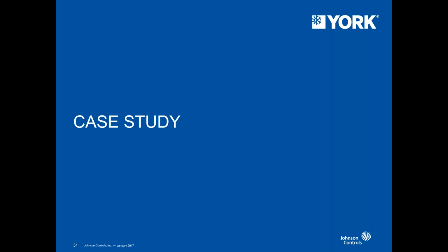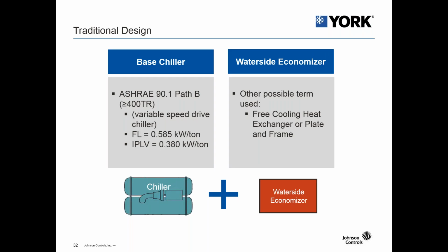So let's take a look at a case study. We're going to first just go through a traditional design with a base chiller and a water side economizer. So we'll just do a quick overview of a schematic. So in a traditional system, you would typically see a base chiller, and for this example, we chose an ASHRAE 90.1 Path B compliant chiller with a variable speed drive. So the full load was a 0.585 with an IPLV of a 0.38.